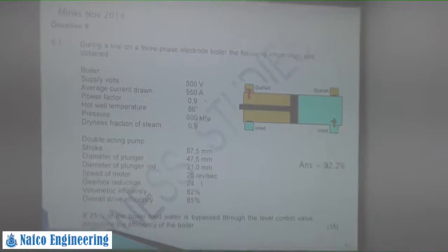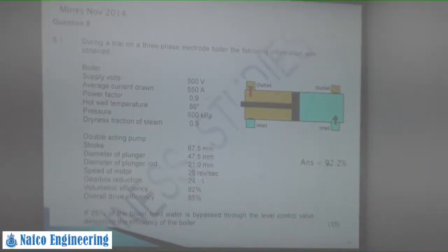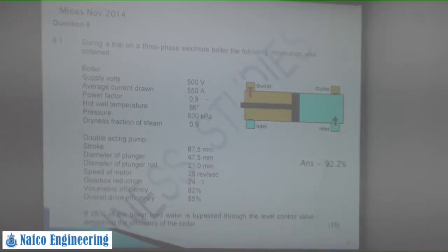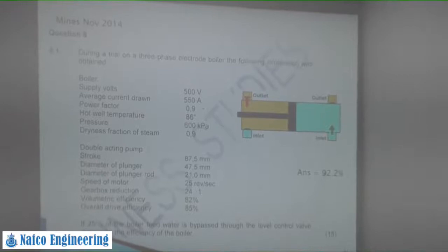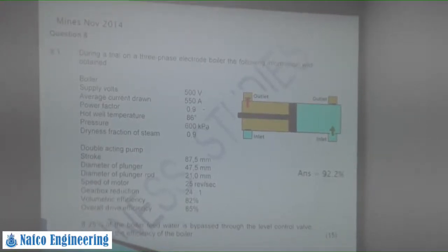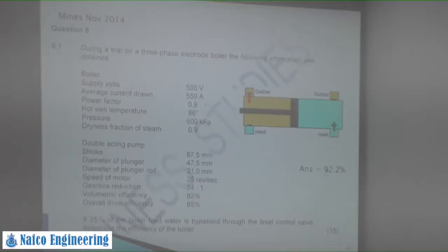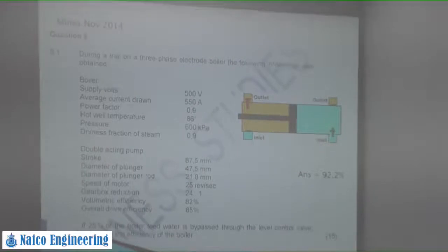Okay. And then the next thing again is a double acting pump. The pump stroke is 87.5 millimeter. Diameter of the plunger is 47 millimeter. Diameter of the plunger rod is 21.0 millimeter. Speed of the motor is 25. And then gearbox reduction is 24:1. Volumetric efficiency is 82%. And then overall drive efficiency is 85%.